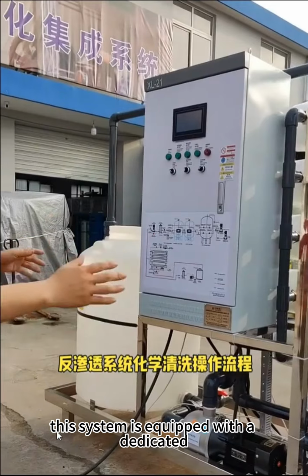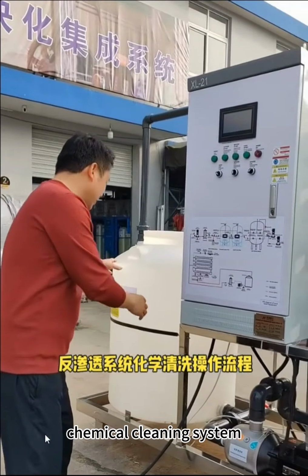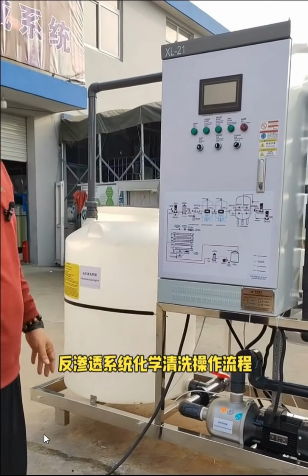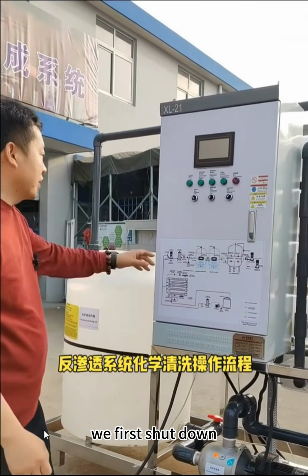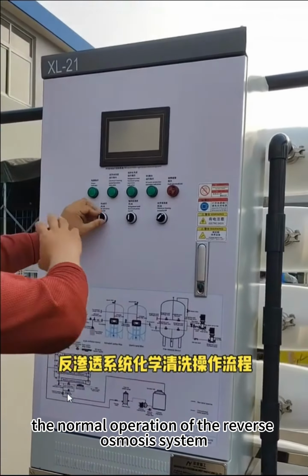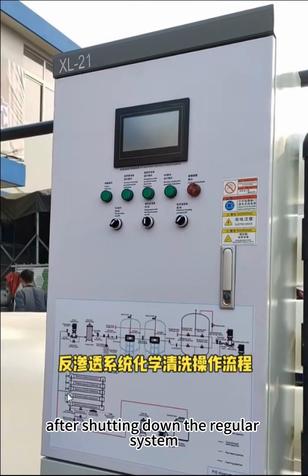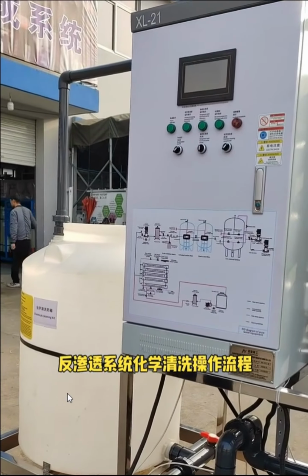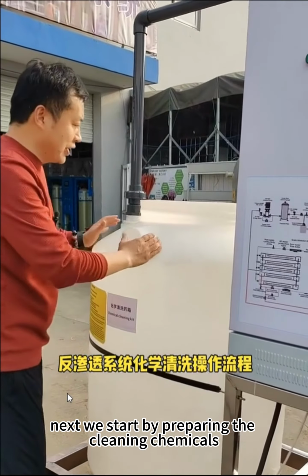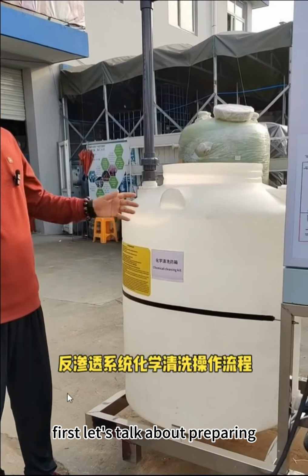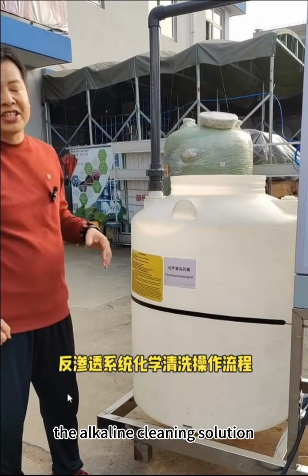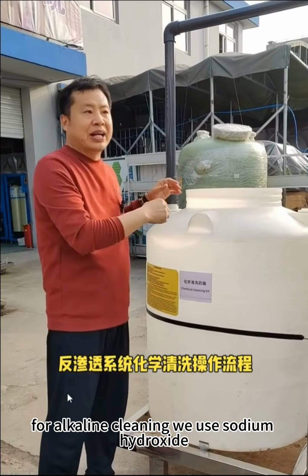This system is equipped with a dedicated chemical cleaning system for the reverse osmosis membrane. Before cleaning, we first shut down the normal operation of the reverse osmosis system. After shutting down the regular system, next, we start by preparing the cleaning chemicals. First, let's talk about preparing the alkaline cleaning solution. For alkaline cleaning, we use sodium hydroxide.